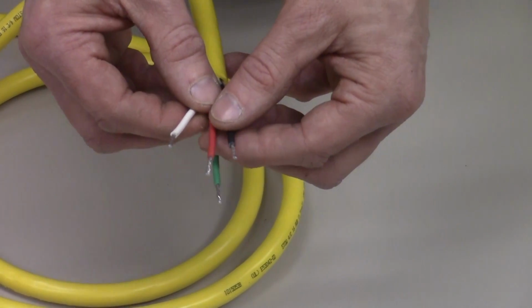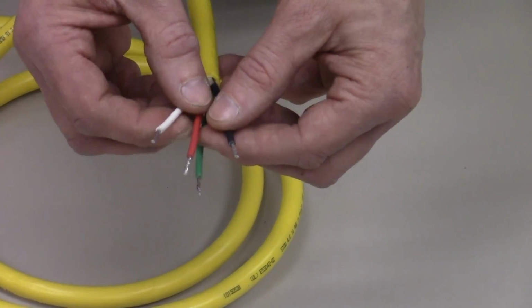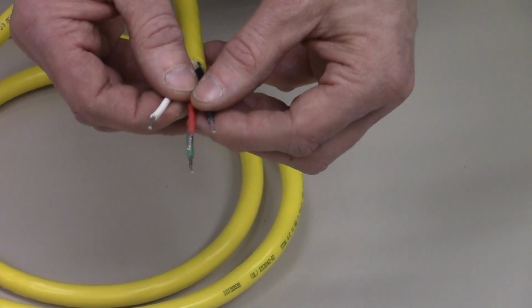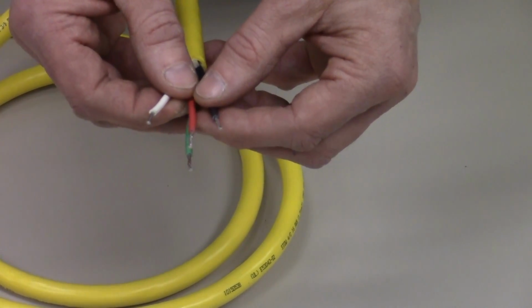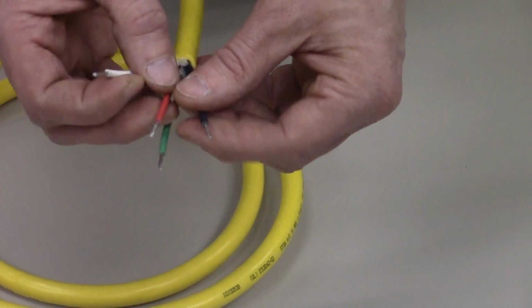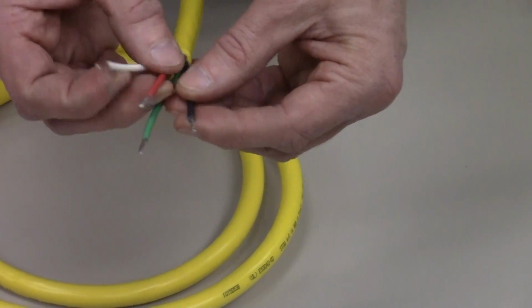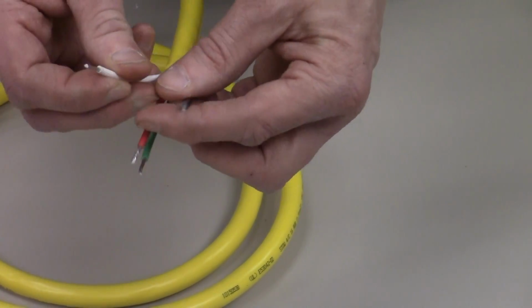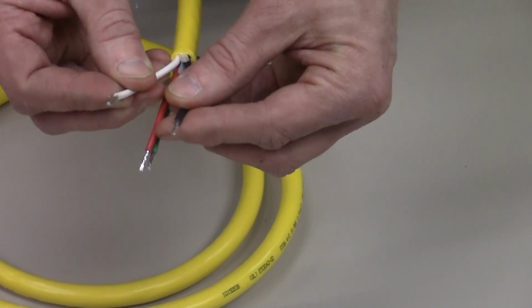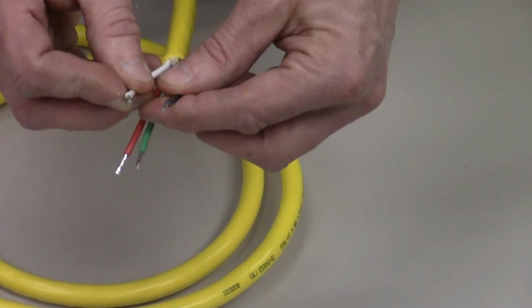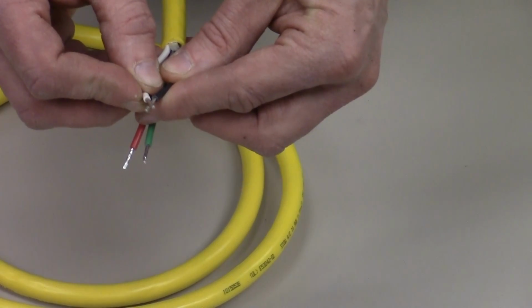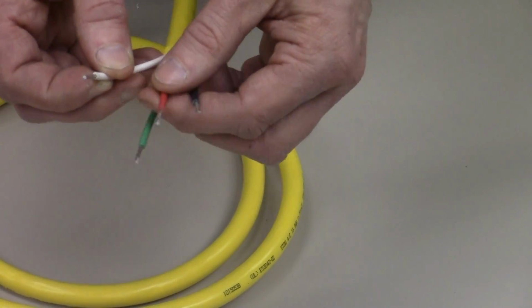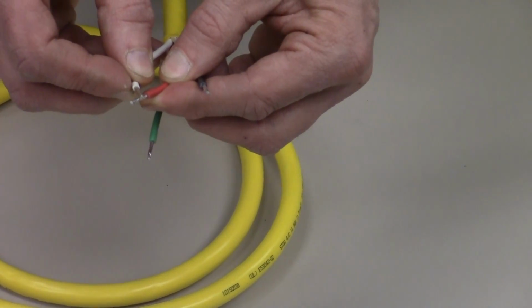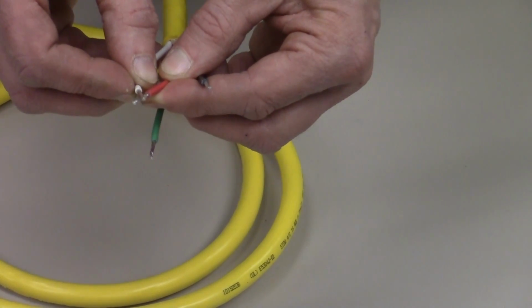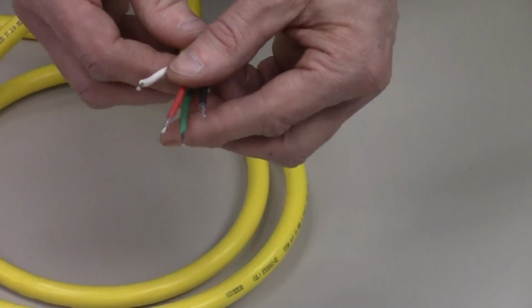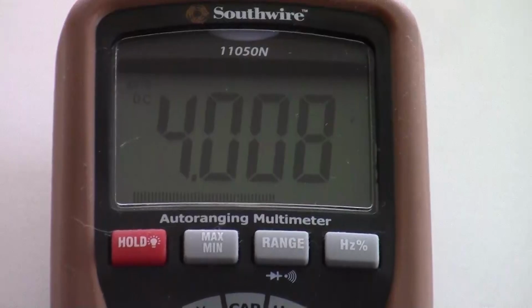To reprogram the 20 milliamp position on the sensor, you move the float to the desired position for 20 milliamps. You will apply power to the red and black power wires, and then short the white program wire to the black wire for 3 seconds, break for 3 seconds, and then short to the red wire for 2 seconds. Break, and you've reset the 20 milliamp position.